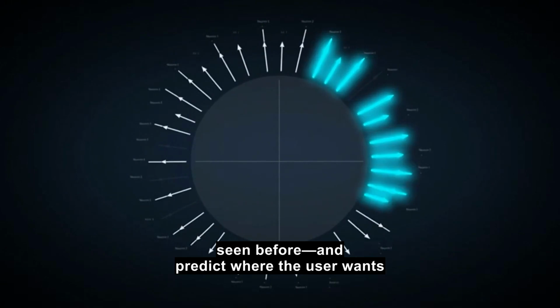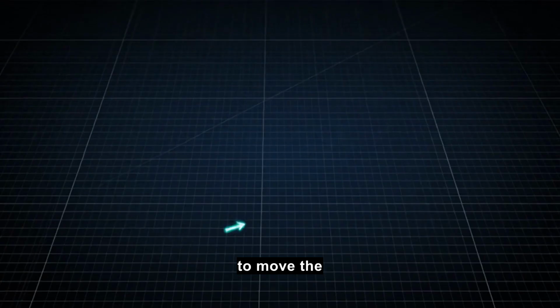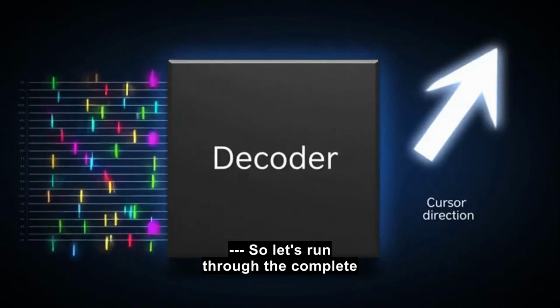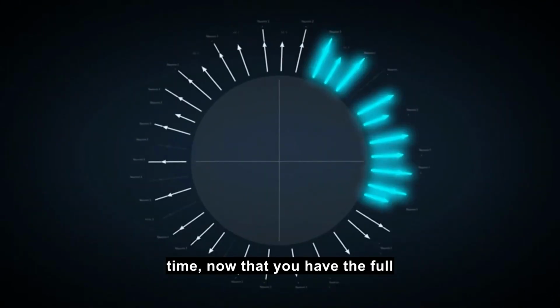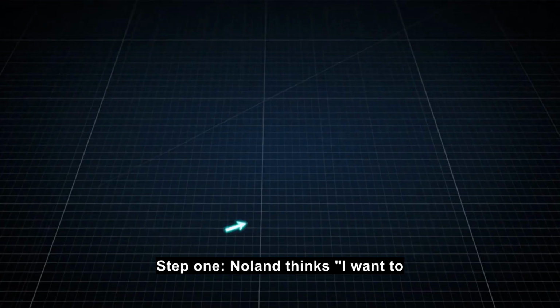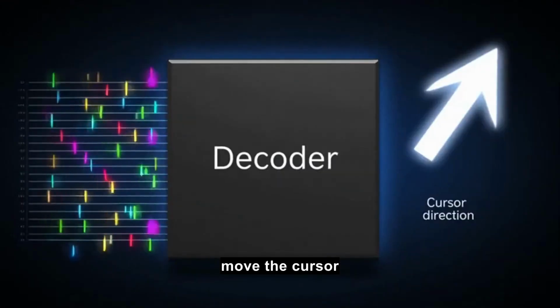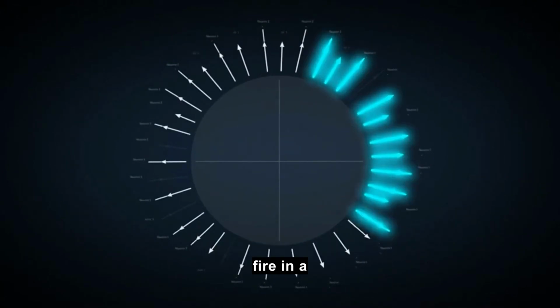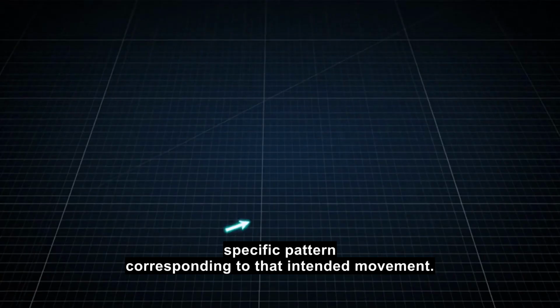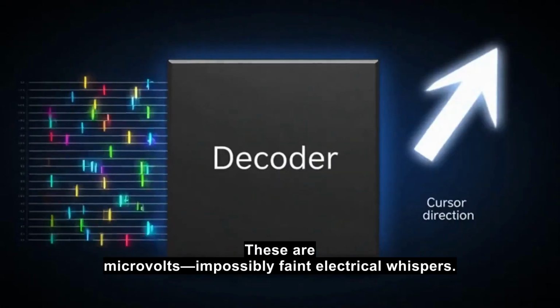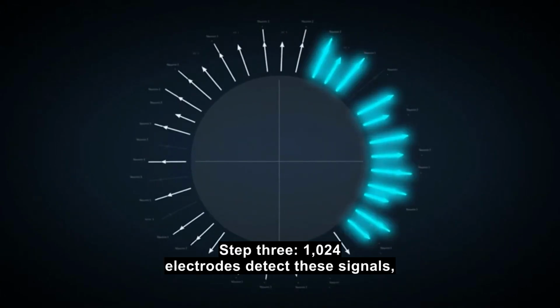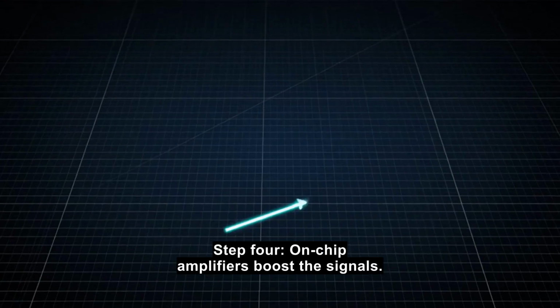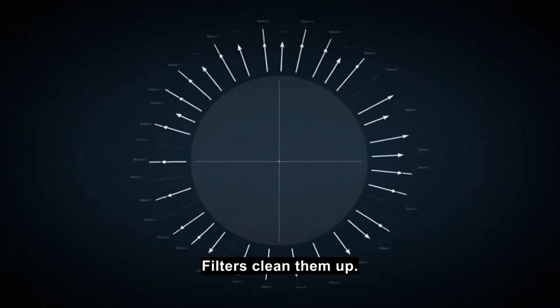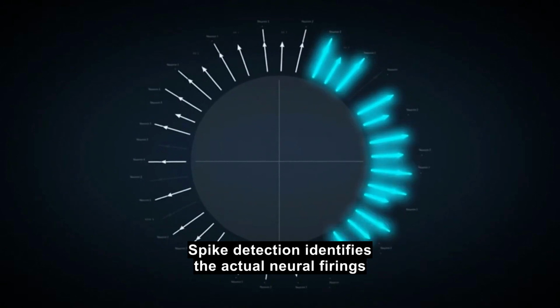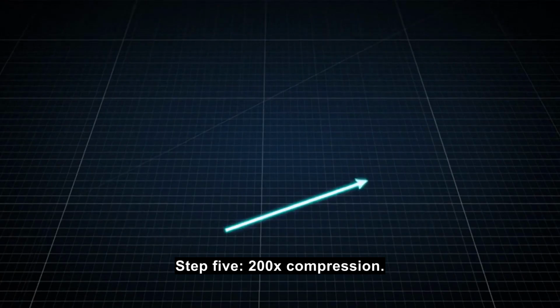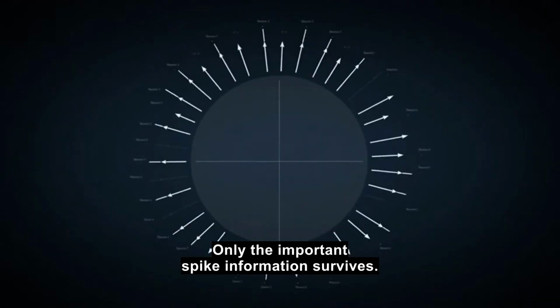Step 1. Nolan thinks, I want to move the cursor up. Step 2. His hand knob neurons fire in a specific pattern corresponding to that intended movement. These are microvolts, impossibly faint electrical whispers. Step 3. 1,024 electrodes detect these signals, sampling 20,000 times per second. Step 4. On-chip amplifiers boost the signals. Filters clean them up. Spike detection identifies the actual neural firings from background noise. Step 5. 200x compression. Only the important spike information survives. Step 6. Wireless transmission. The compressed data beams out of his skull to an external receiver. No wires through the skin.